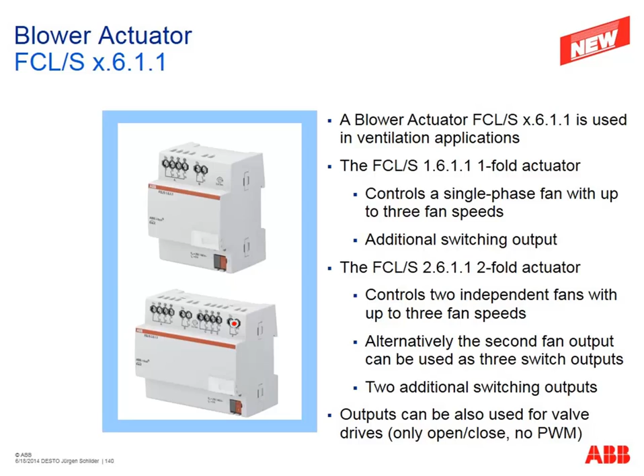And here's the overview of how to use such a blower actuator in a room, for example here in a meeting room. We have a kind of ventilation system. Inside the room we have our room thermostat 6138 to do the heating control inside the room. Additionally, our air quality sensor measures the CO2 concentration and the humidity and sends the values to the KNX bus. Additionally, the device sends different thresholds, and via these thresholds we can control our blower actuator and change the fan speed number 1, 2 or 3, for example.